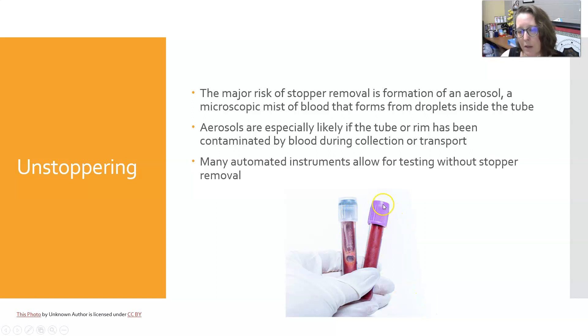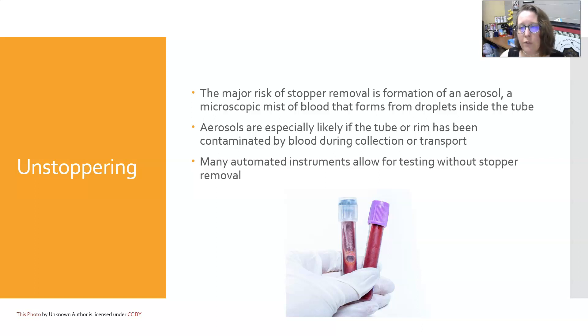Many automated instruments allow testing without stopper removal. For example, the purple top going to hematology is usually tested without stopper removal, while the light blue top must be centrifuged and the lid removed for coagulation analysis. Some instruments are cap-piercing and some are not. If you place a specimen in an analyzer with a cap on when it is not a cap-piercing probe, the probe will crash into the lid and cause an instrument malfunction.